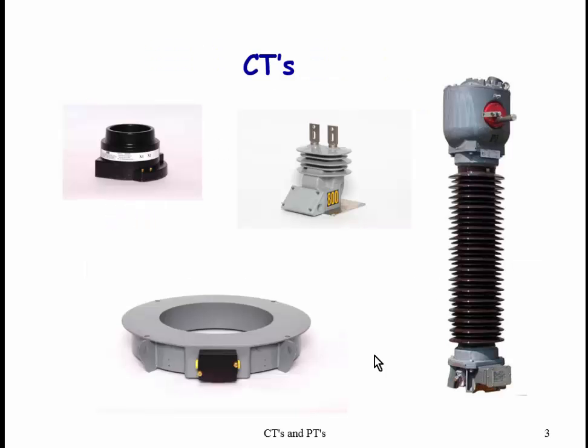So CTs are really pretty simple. Here's some different varieties of them. This one is what we might call a donut CT. Essentially, you take the large power conductor, it goes right through the middle of the hole here. This CT, of course, the wire is cut and attached to each end here. So the primary goes through the inside of this CT and then out, and the secondaries of the CT are connected right here. And then here's a high voltage one.